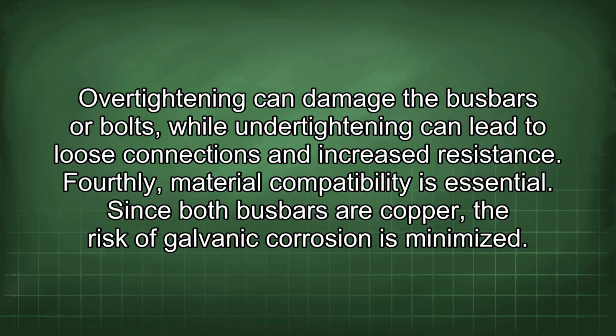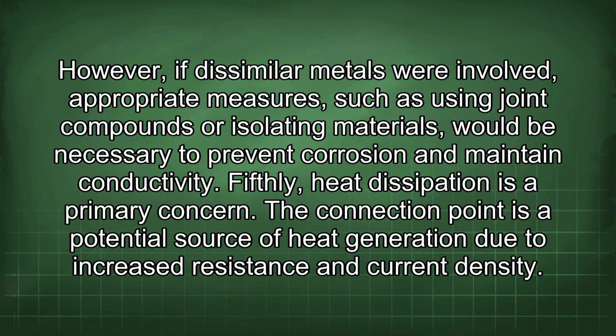Fourthly, material compatibility is essential. Since both bus bars are copper, the risk of galvanic corrosion is minimized. However, if dissimilar metals were involved, appropriate measures, such as using joint compounds or isolating materials, would be necessary to prevent corrosion and maintain conductivity.